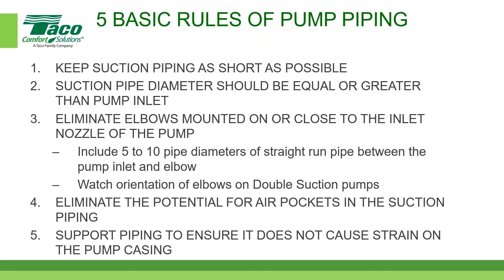And then eliminate air pockets, right? The ups and downs in piping, eliminate that. Get rid of that. Don't do that. And then pipe away from pumps. Don't pipe to pumps, right? So you don't want to put strain on the pump casing. That can knock things out of alignment. You'll have to remount things to the base, or try to realign the motor and the coupling. So really support the piping, and pipe away in that regard.